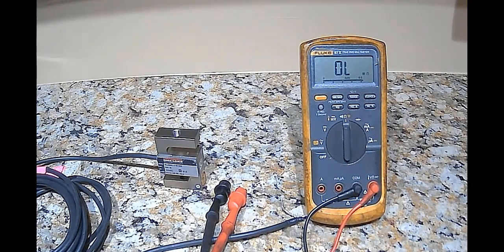If you do not have access to a mega ohm meter, you can also find if a cell has moisture by removing one cell from the J-box. And if the scale stabilizes, then this cell likely has moisture and needs to be replaced. Never try drying out the cell even though it may work. It will only last briefly because once moisture has penetrated the wire or the cell, it will continue to do so. Replace the cell.